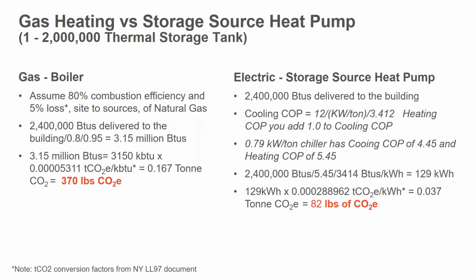What I decided I would do is look at one of those energy storage tanks. Okay, so about 2 million BTUs in that tank. And so if you look at the energy associated with getting that from a gas boiler, and let's say it was 80% combustion efficiency, 5% for getting the gas to the building, site source, we're going to end up delivering a total of 2.4 million BTUs to the load. Okay, that's the overall plan, and I'll tell you in a second where we're getting the extra energy from. So to do that with the gas boiler, you'd need about 3.1 million BTUs.